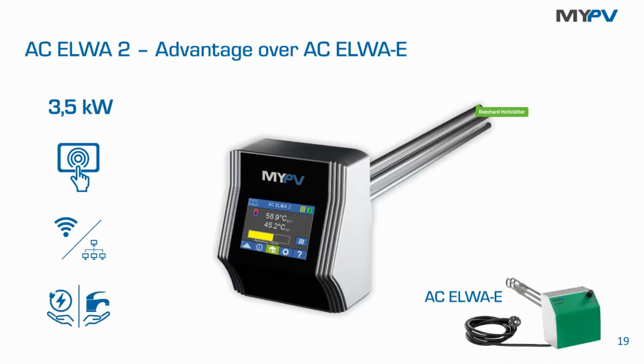Compared to the older generation, it has 4 major benefits. It now has more power output, and more power output means a higher self-consumption ratio and a higher autarky rate. Then there's a graphic user interface. There's a color touch screen, which makes the commissioning very easy. You have the option to communicate, additionally to the RS485 bus with IME, either via LAN or Wi-Fi.